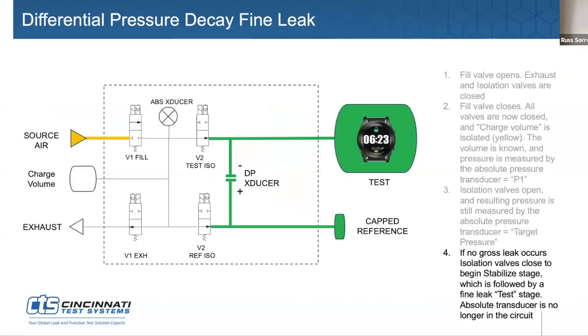So here's a differential pressure decay circuit. Makes more sense here. Yeah, so a DP circuit uses a source air. You pressurize your test part and this referenced capped volume through these open valves. The valve in here that's closed is V1 exhaust. That's closed to exhaust as the whole system fills up with pressure.